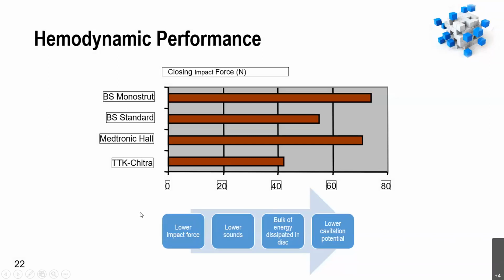Then another major factor to be looked at is what is called the closing impact forces. Impact forces means when the valve closes, there will be some impact energy, and how much force is generated during the closing mechanism or closing dynamics. And it is better to have lower impact forces. If you look, these are the other predicate devices which were in the market at that point of time. We found that the impact forces of the Chitra valve are relatively low. This was mainly because all other models used a particular material called pyrolytic carbon. Pyrolytic carbon is basically low temperature isotropic carbon with a density of somewhere about 2.4 to 2.5 and hardness close to that of alumina or diamond. That means it's an extremely hard material, and the relative difference between the density of blood and that of this material is very high, leading to high impact forces.